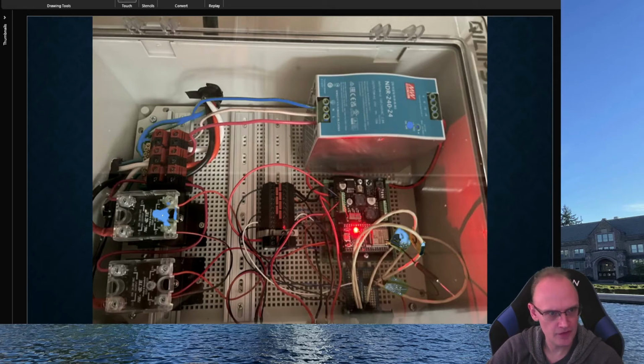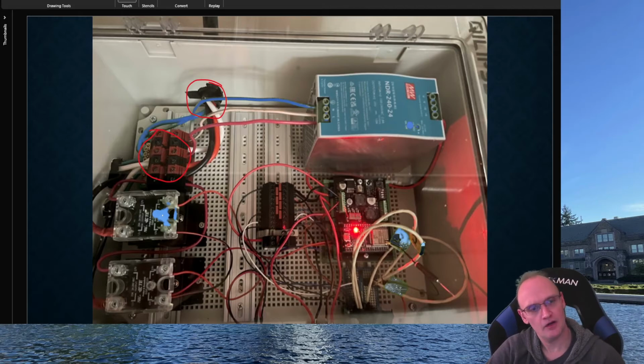Okay, so back to the top of the panel. Here's where we have our 50 amp circuit incoming. And this is going into a terminal block here where I can break it out into a couple different areas. So there's one hot going to each of these SSRs, solid state relays. These are what enable the low power side of the board to actually turn the heaters on and off. So one of these wires coming in is a low current on and off signal for the relay. And then on the other side, we have our 2 hots coming in for our 240 volt circuit to actually deliver the amperage to the heaters.